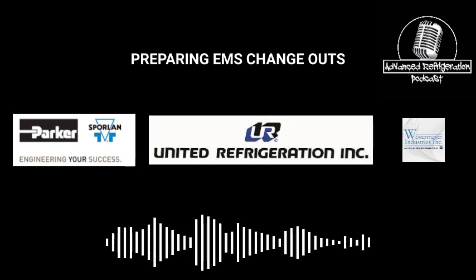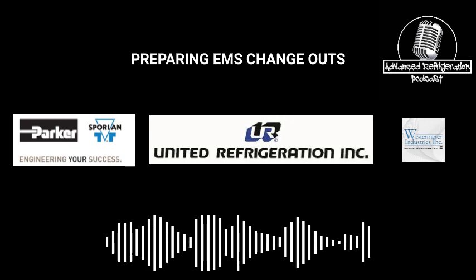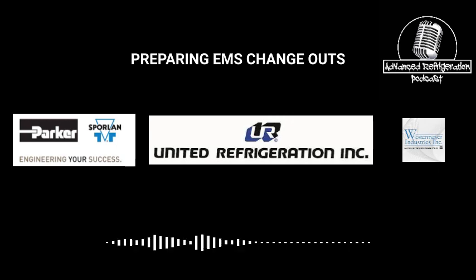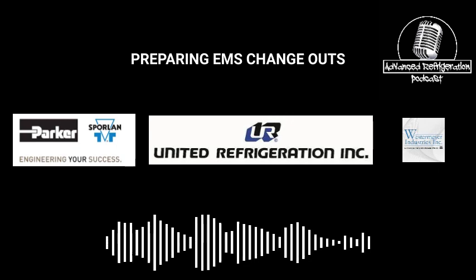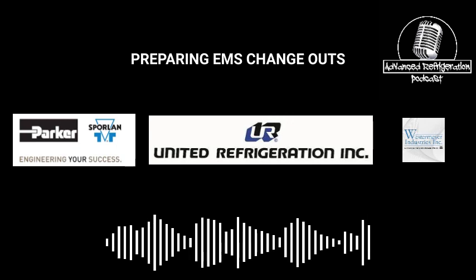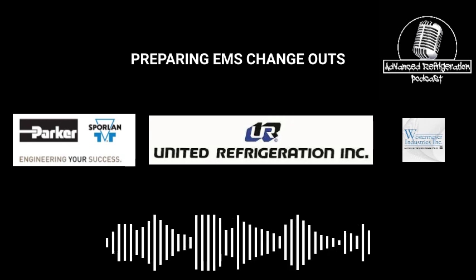Every switch gets checked, make sure everything's at temp, make sure there's not compressors banging on and off, make sure condenser fans are working, be very diligent before you leave the building. You don't want to leave a bunch of stuff down and then somebody ends up there or you end up with a product loss. I mean, that's an easy way to tank one of these jobs, a product loss, or having the service department come out a bunch of times because you're forgetting to turn stuff back on. You move some wiring around and you lost a common. I mean, let's be honest, some of these racks are on their second or third retrofit. So you're going to have times where you move a wire and it kills something else. So just be very diligent about that and make sure that you're doing it properly.